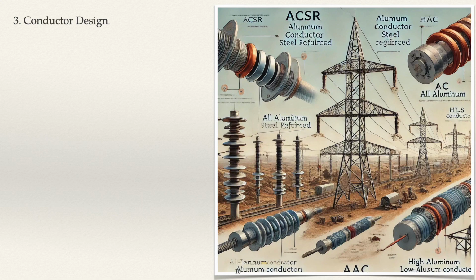High voltage lines require larger conductors to minimize corona loss and maintain voltage stability. 5. Sag and tension. Conductor sag must be minimized to maintain ground clearance and prevent safety hazards. Tension calculations ensure the conductor can withstand mechanical forces without excessive sag or snapping.